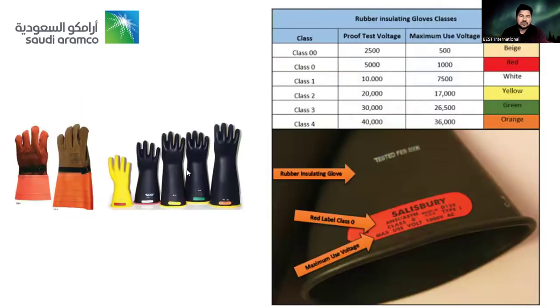Now, according to the classes, there are rubber insulated gloves. If you are buying class 00, then the proof test voltage is 2500 and the maximum use voltage is 500. Label color is there. If class 0, the proof test voltage is 5000 and the maximum use voltage is 1000. Class 1 is 10,000. So according to the class and the proof test voltage, the higher the voltage, the maximum use voltage is mentioned also, and the color is also highlighted. According to this spec, you have to use the rubber insulated gloves.